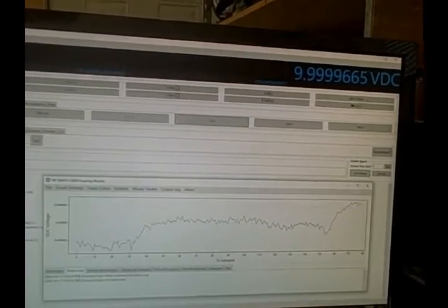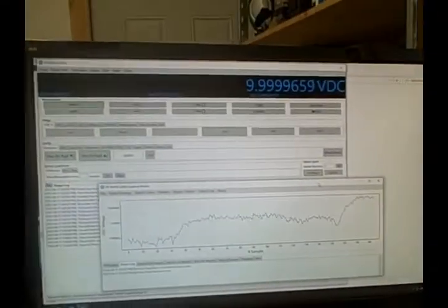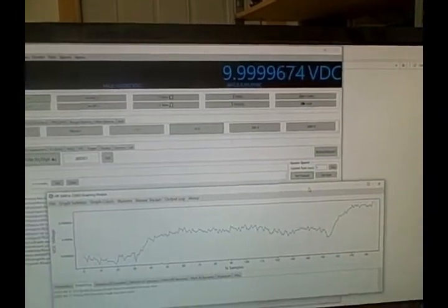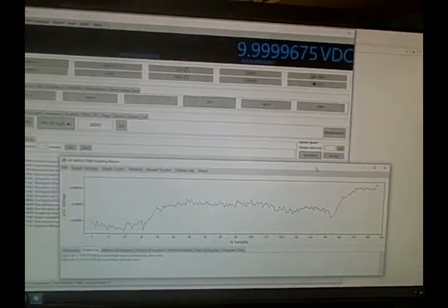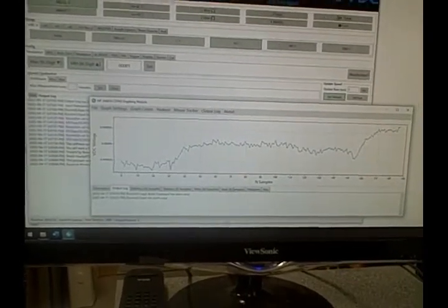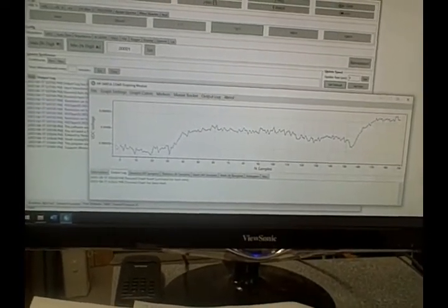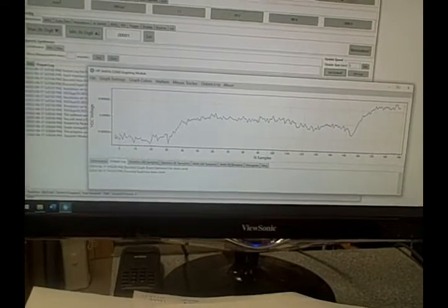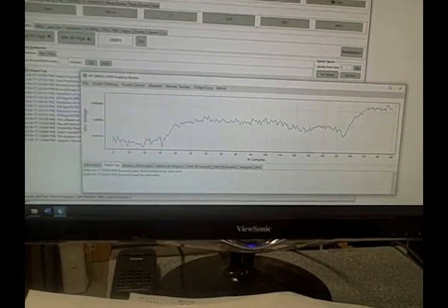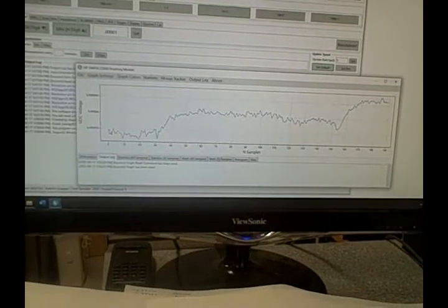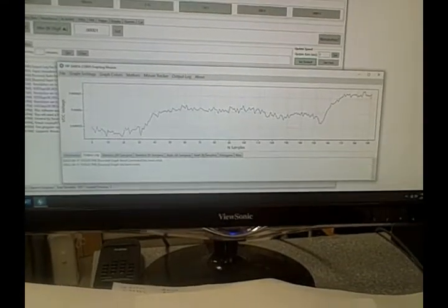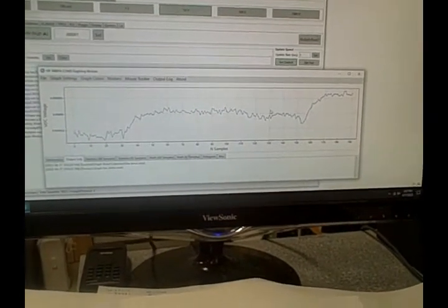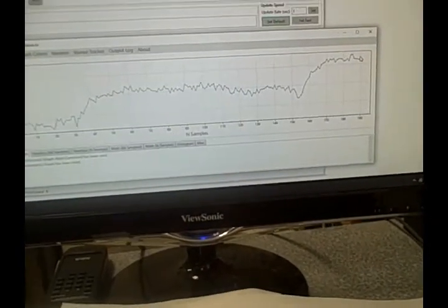We'll put the graph on it as well. So I am really geeked about this software. This is fabulous stuff. Since I started warming up this unit, when I first turned on the 34401A and I had 10 volt reference plugged into it, we started out at zero samples and right at the moment we have total samples of 1071. It does some averaging and plotting and here's the graphical plot of this thing.